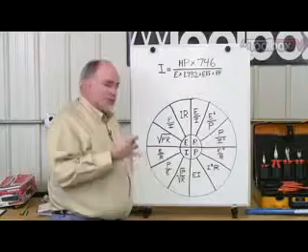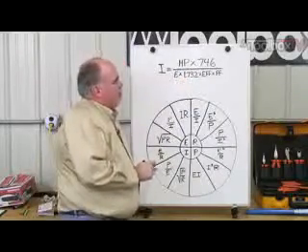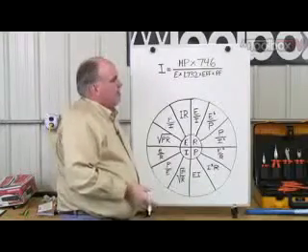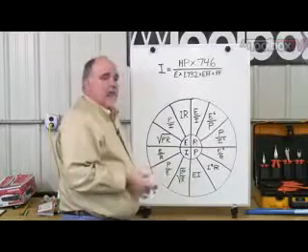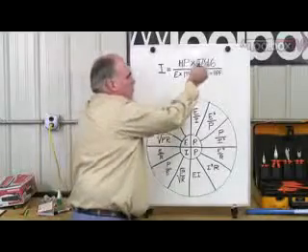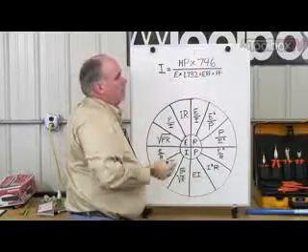Now, let's look at a formula for calculating the current for a three-phase induction motor. Now, if you look at this, it looks kind of full, all kinds of stuff in it. The top of it, horsepower times 746. 746 is a constant because there's 746 watts of power consumed per horsepower in an electric motor. So what we're doing here is converting horsepower to wattage. So the top of this formula becomes power. Okay? So forget this. Now we got our power.